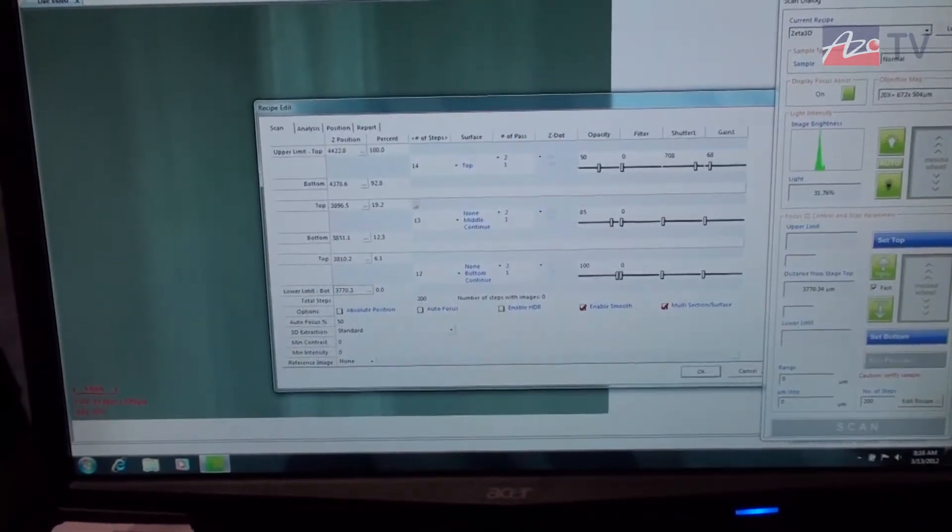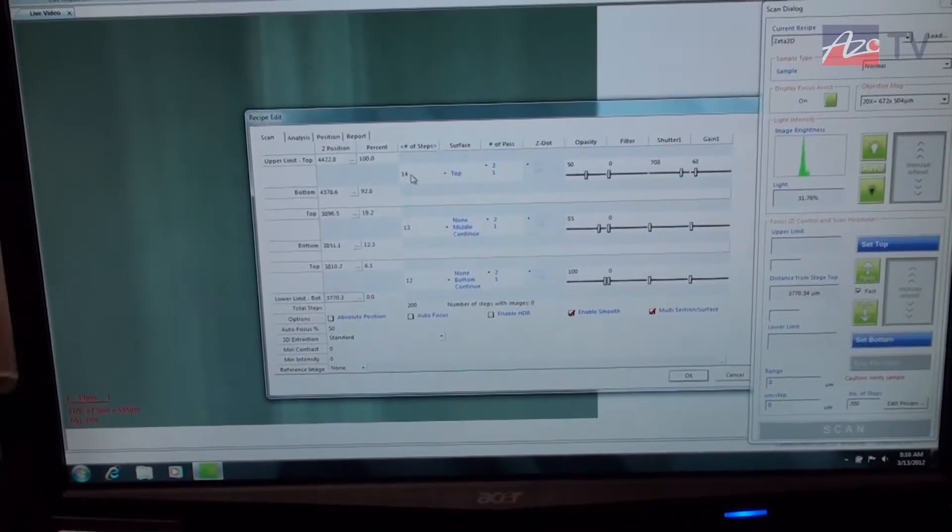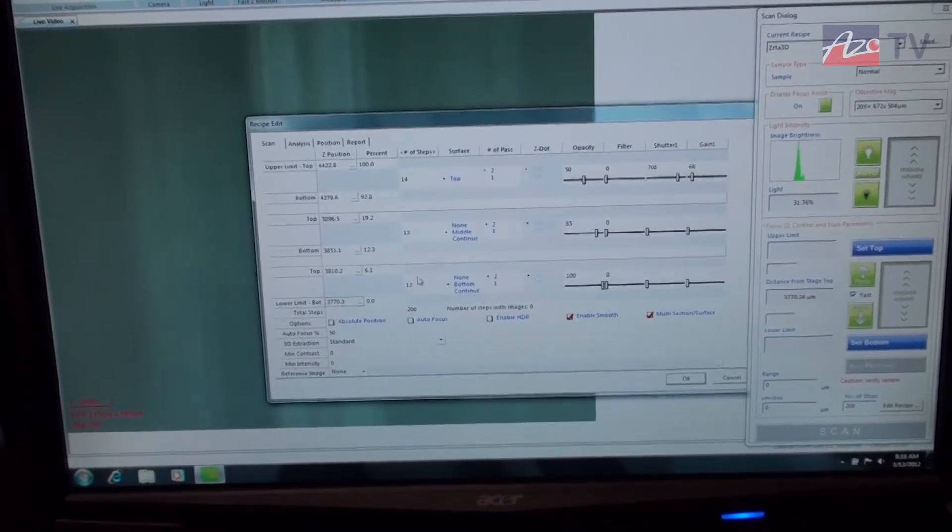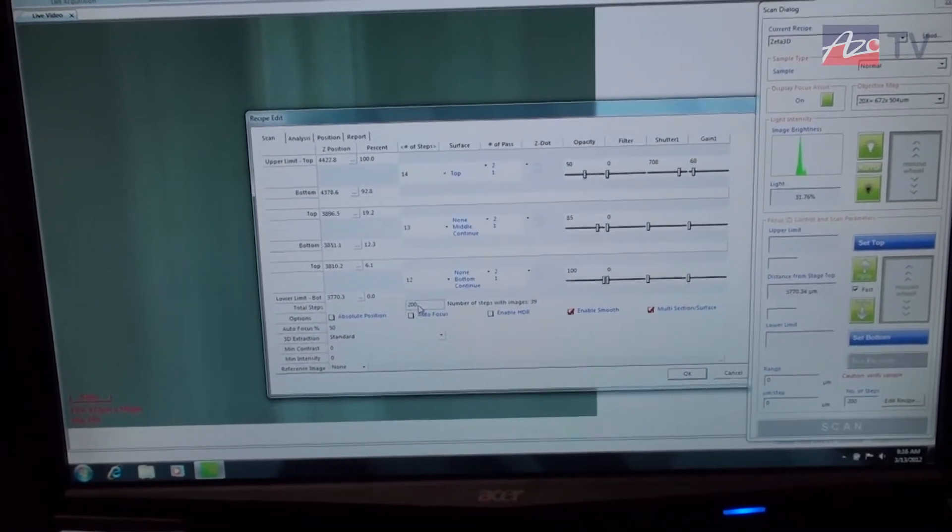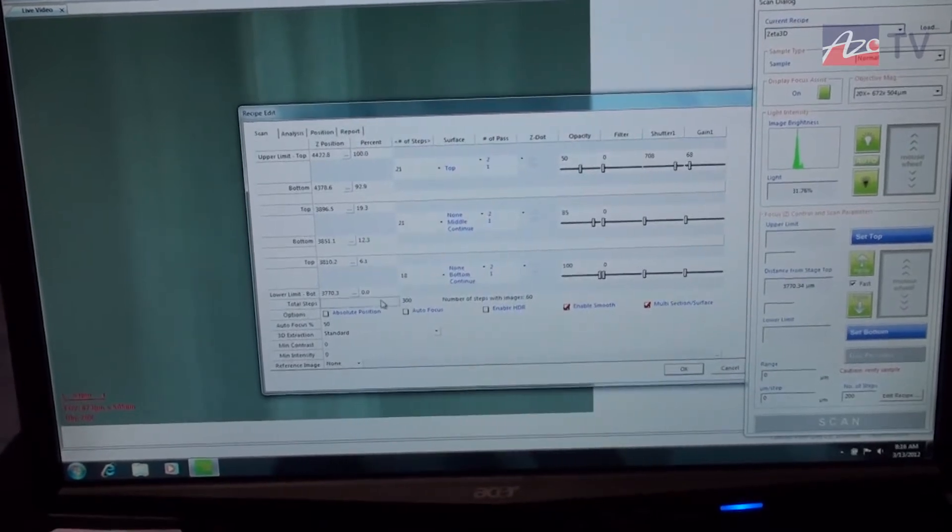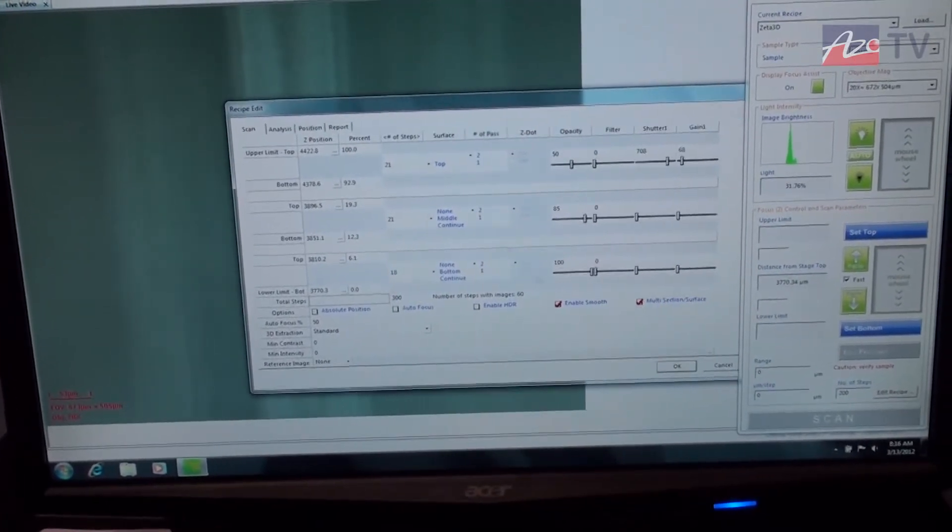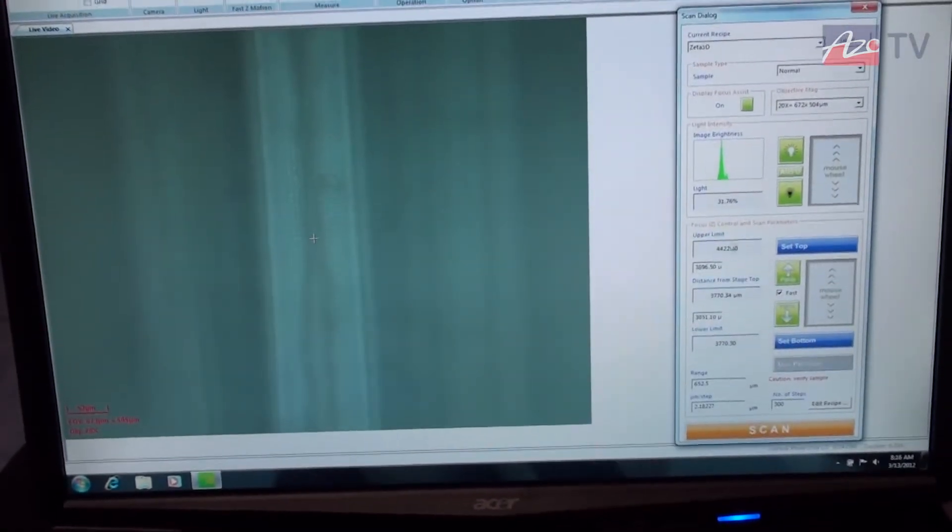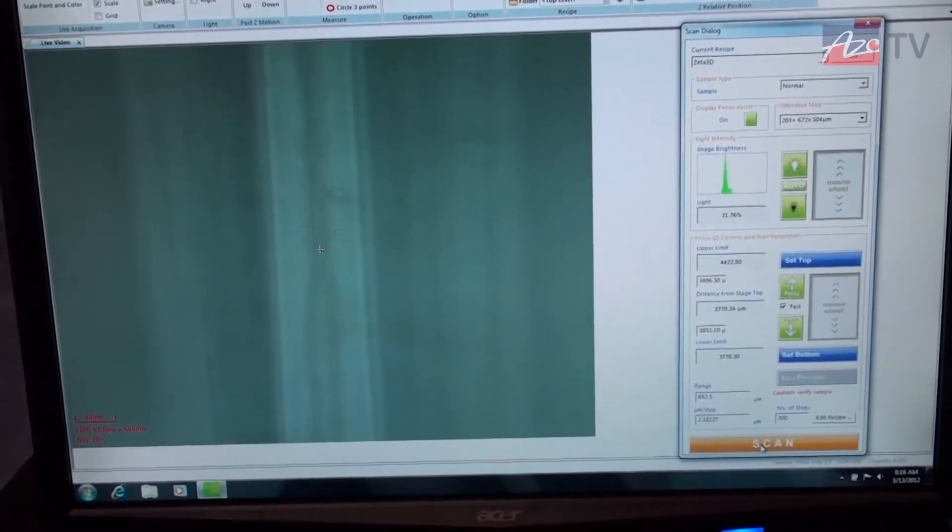So at this case, what we're going to do is collect or resolve 14 scans for the top, 13 for the middle, and then 12 for the bottom. Or let's go ahead and just increase that. So maybe I'll adjust this to something like 300, in which case it will increase the slices. Let's go ahead and say OK. On our software interface, what it does now is it actually puts in the different layers for the scan.